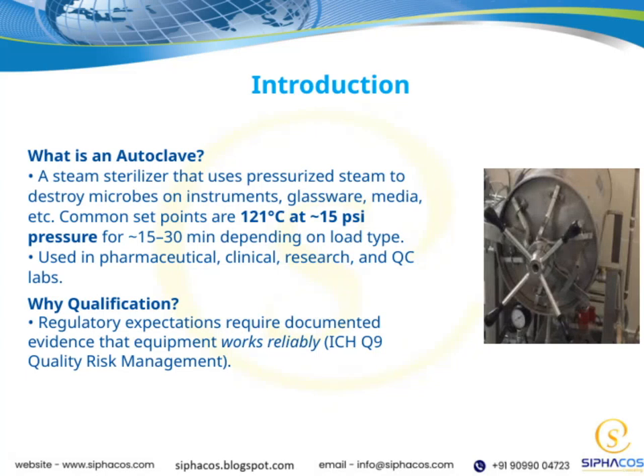Let's start by understanding what an autoclave is. Essentially, it's a steam sterilizer that uses pressurized steam to kill microbes on various items such as instruments, glassware, and media. The typical set points are around 121 degrees C at roughly 15 psi pressure, and the sterilization cycle usually lasts between 15 to 30 minutes, depending on the load type. These devices are widely used across different fields like pharmaceutical, clinical, research, and quality control laboratories.